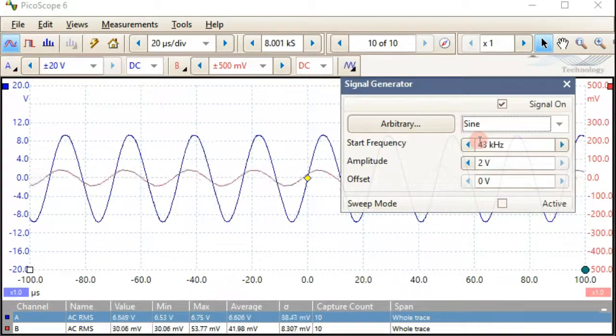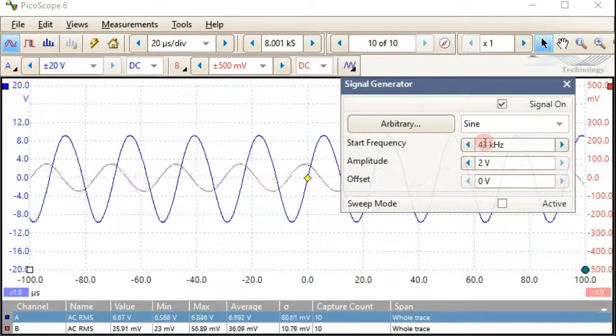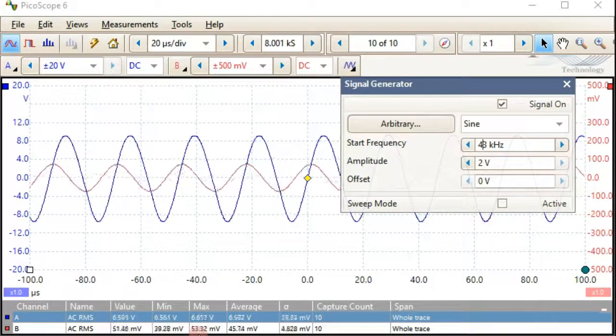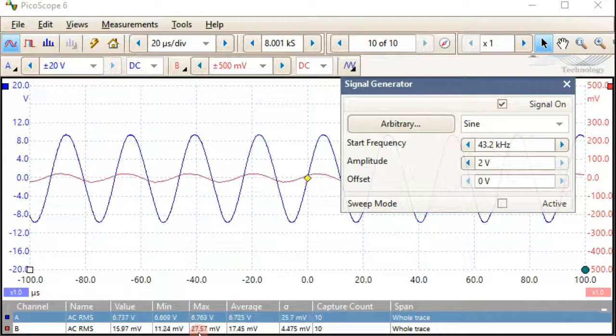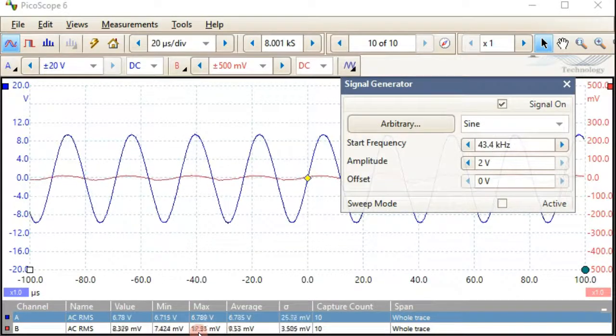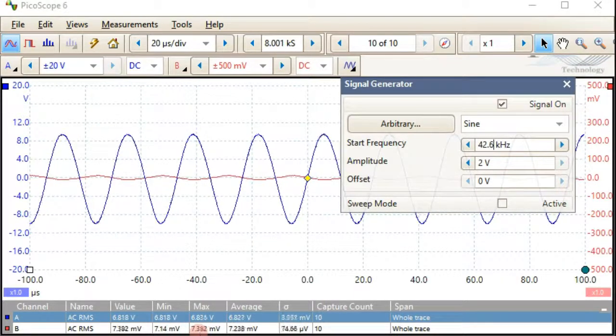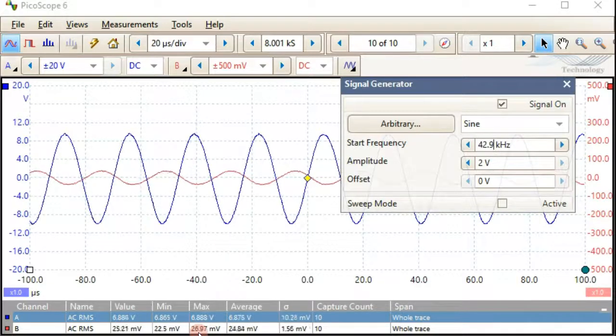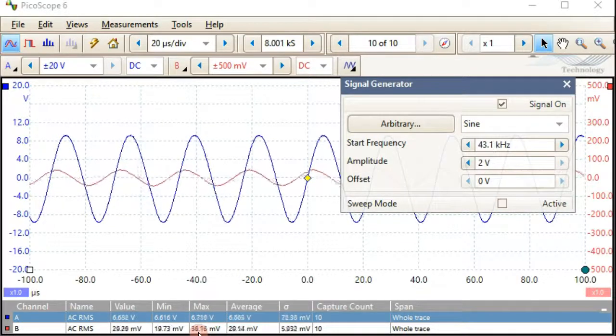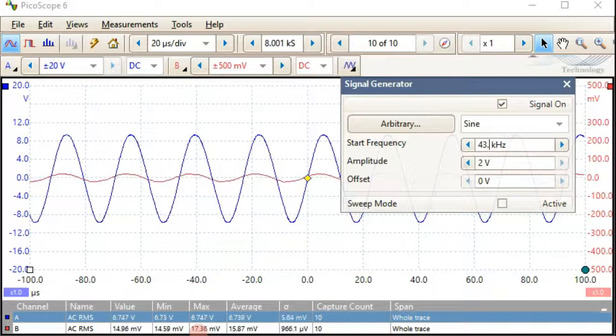If you do change to 43, what we would like to do now is just get an estimate. The maximum amplitude we're getting is about 50 millivolts, right? So if I type in 43.34, we're actually past the resonance. So let's try 42.5, 42.6, 42.7, 8, 9. Seems to be at 43 actually. 41. I seem pretty close to 43.